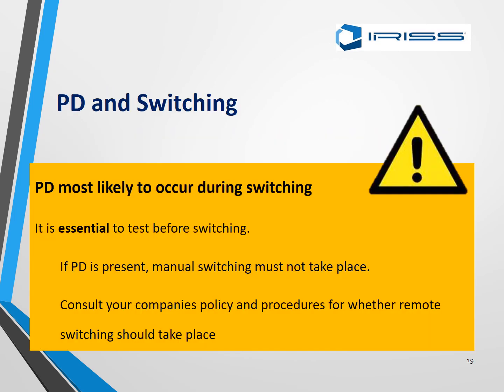It is a rule of thumb that it is essential to test before switching. So if PD is present, manual switching must not take place. What you need to do is consult your company policy or procedures to determine whether remote switching should take place.